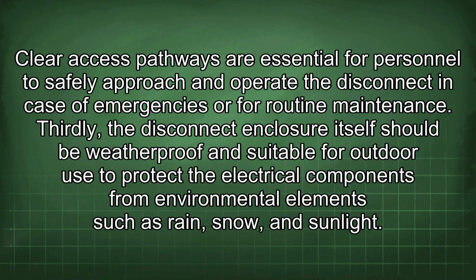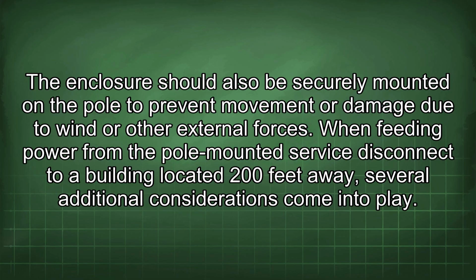Thirdly, the disconnect enclosure itself should be weatherproof and suitable for outdoor use to protect the electrical components from environmental elements such as rain, snow, and sunlight. The enclosure should also be securely mounted on the pole to prevent movement or damage due to wind or other external forces. When feeding power from the pole-mounted service disconnect to a building located 200 feet away, several additional considerations come into play.